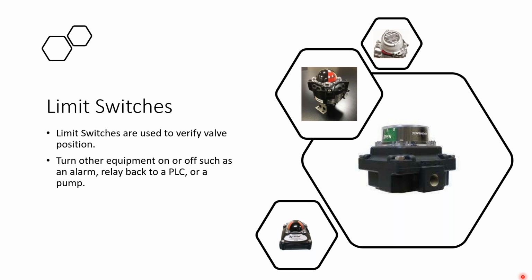Yes. So the proximity switches have gotten better throughout the years, and I think I understand the question, because the proximity switches in the past have typically not been as reliable as a mechanical switch. The improvements made in recent years have increased greatly. We have customers who cannot afford a limit switch with a mechanical device where there's any chance of an explosion. So the proximity switches are used in that application where there are no moving parts.